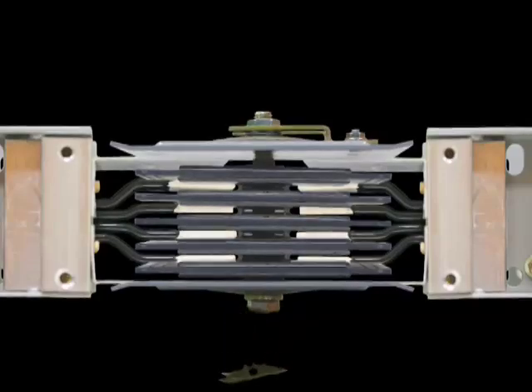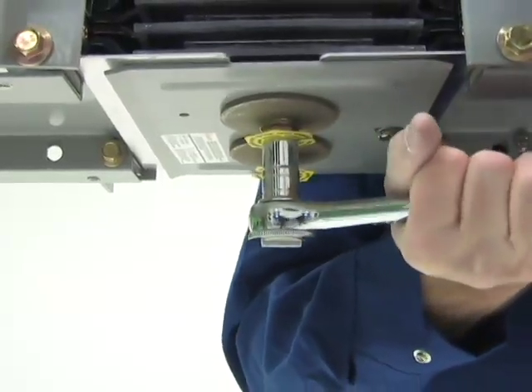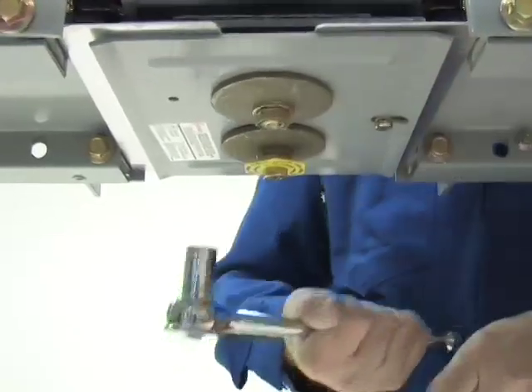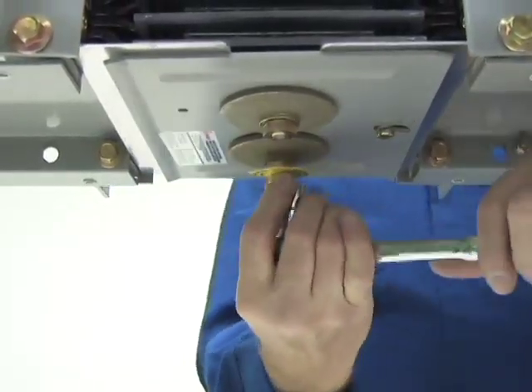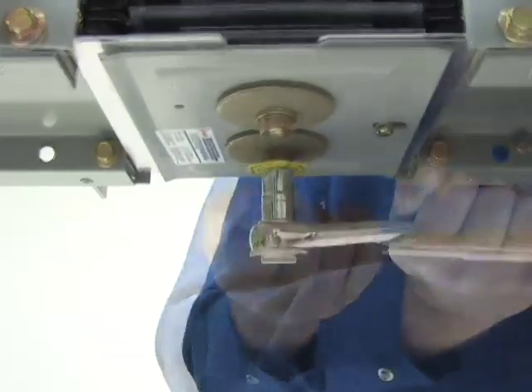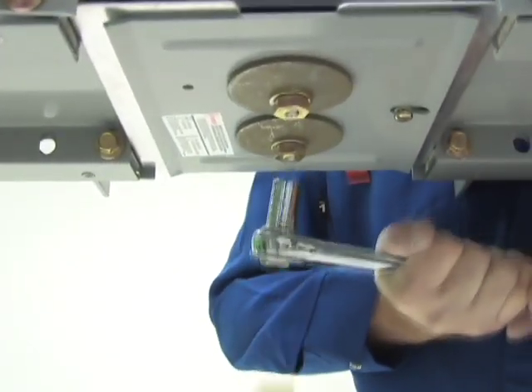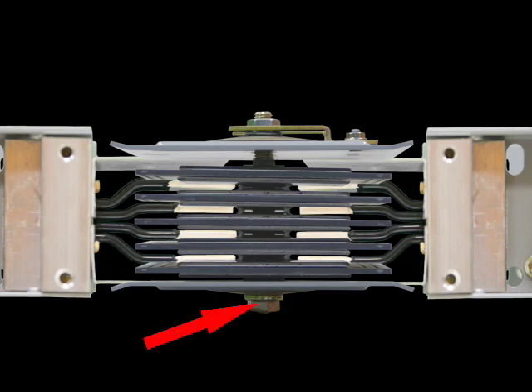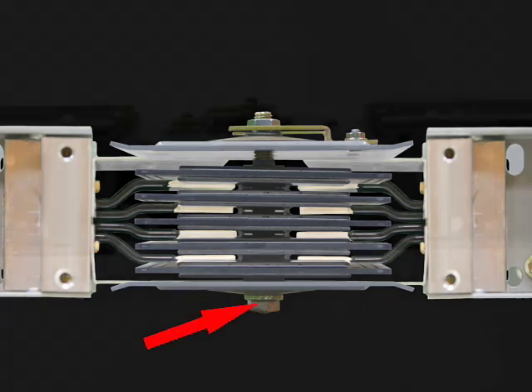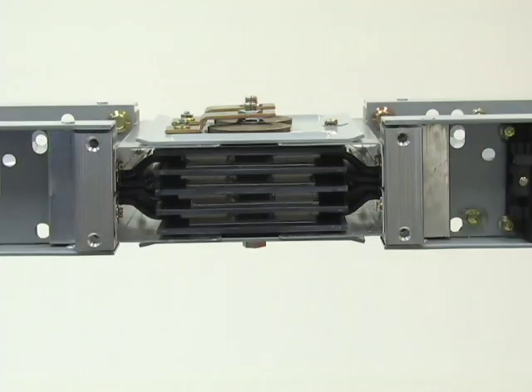Fall-away instruction tags are provided between the upper and lower bolt heads. A standard socket wrench with a minimum 14-inch handle should be used to tighten the joint bolt. When the proper torque is achieved, this bolt head will shear off, allowing the tag to fall to the floor. The inner bolt head remains intact for future maintenance. After each joint bolt has been tightened to the proper torque, the joint covers may be installed.